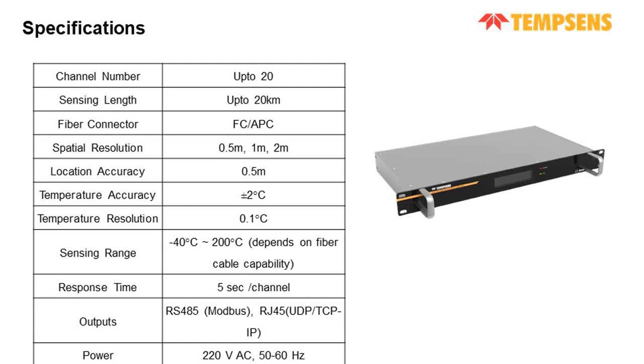Now, this is the specification for the Dtsenz system. There can be up to 20 channels, so you can connect 20 sensor fibers on a single controller. The sensing line can be up to 20 km per channel. So 20 into 20, you can measure 400 km.